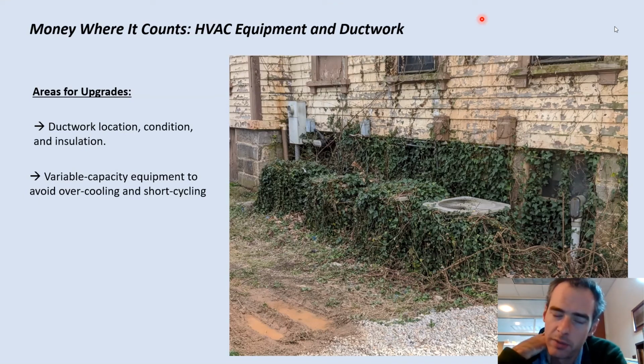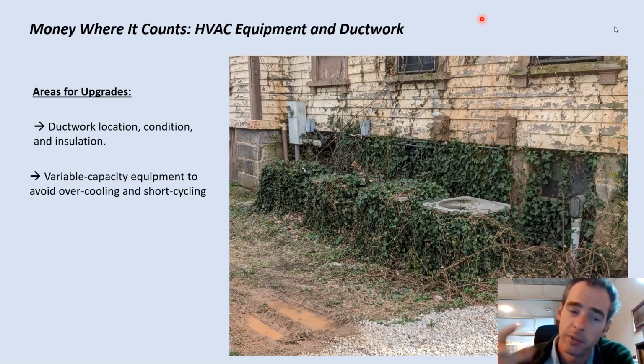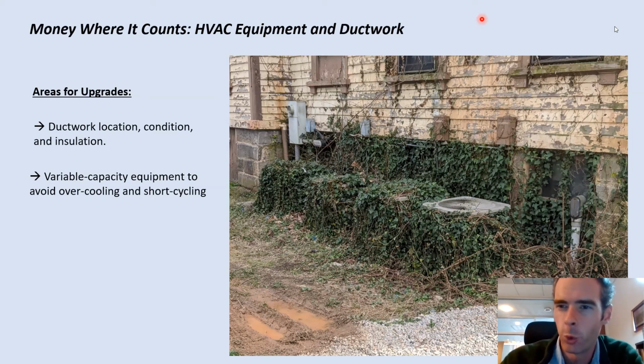The advantage to variable capacity equipment is that you don't experience short cycling. Short cycling occurs when you have a large, overpowered, oversized air conditioning unit servicing a space, so when you set the thermostat to say 72 degrees, the system is so robust and powerful it reaches that quickly and shuts off. When that happens, you don't get sufficient dehumidification in the space, and you'll often get a cool but clammy, uncomfortable environment, which you encounter in a lot of buildings in the South in the summer.